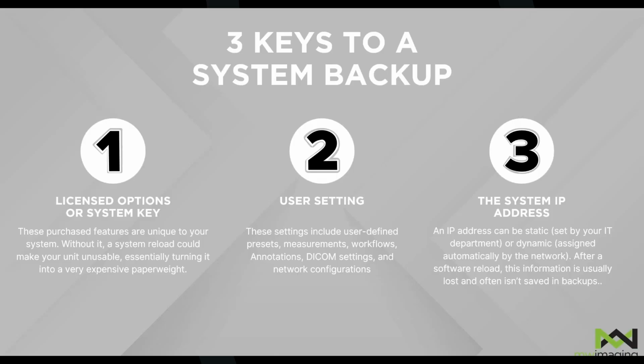The second thing, after you make sure that they have the license option settings, you want to make sure that they have the user settings. These settings are user-defined presets, measurements, workflows, annotations, DICOM settings, and network configuration. And the third thing you want to make sure that they have is the system IP address, or know the network that they're on, whether it's wireless or wired, and whether it's a static or a DHCP type network IP address.